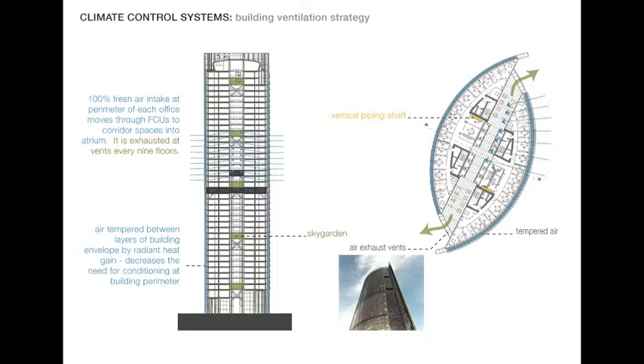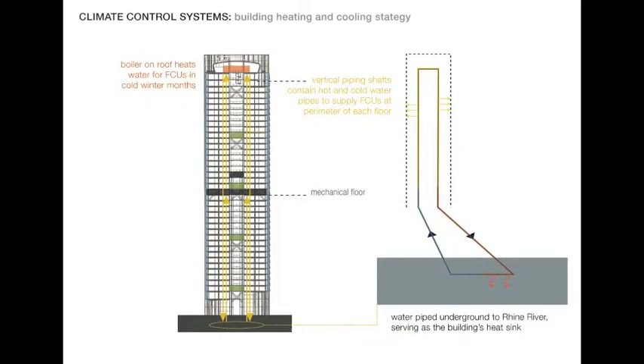The building uses 2 types of mechanical climate control systems: the FCUs, located at the building perimeter, and hydronic radiant heating and cooling. In the summer, water for the FCUs is cooled through a closed-loop heat sink piping system. This system carries warmer water from the building to the Rhine River, where heat is lost from the pipes to the river water. This cooler water, about 55 to 60 degrees Fahrenheit, is then returned to the FCUs to condition air at entry to the building perimeter. The water is cool enough that the building does not require a chiller at all.